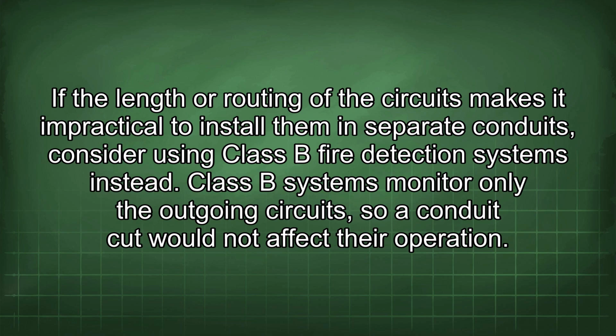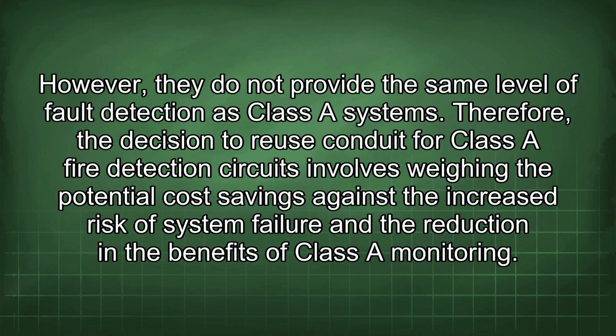Class B systems monitor only the outgoing circuits, so a conduit cut would not affect their operation. However, they do not provide the same level of fault detection as Class A systems. Therefore, the decision to reuse conduit for Class A fire detection circuits involves weighing the potential cost savings against the increased risk of system failure and the reduction in the benefits of Class A monitoring.